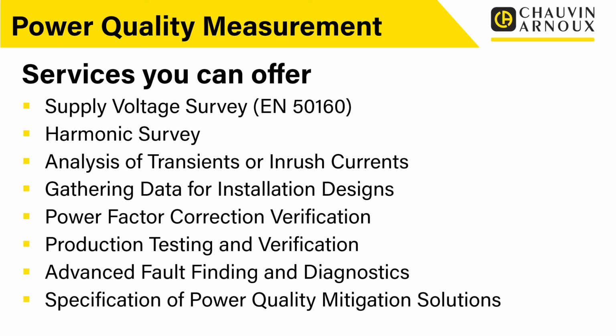One of the main things you'll see power quality analyzers used for is advanced fault finding and diagnostics. Generally, when you do a logging session, or some trend analysis with your power quality analyzer, you'll start to pick up a few issues. You might get some alarms coming through. That's when you want to start digging in, actually fault finding, breaking it down into individual circuits, isolating, turning off bits of equipment or parts of the installation.